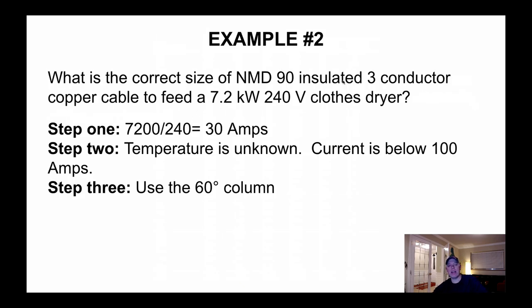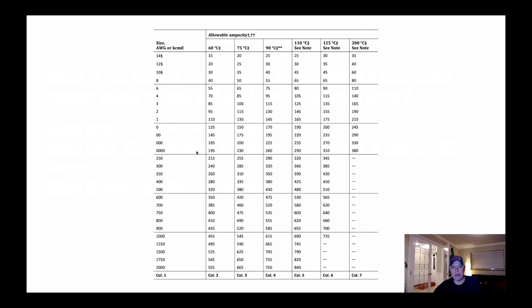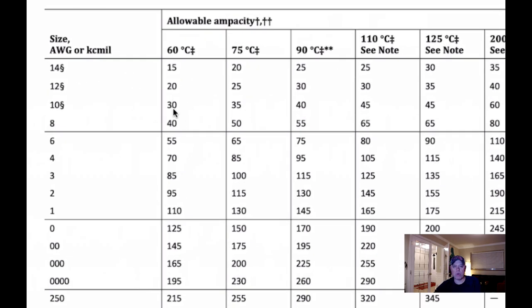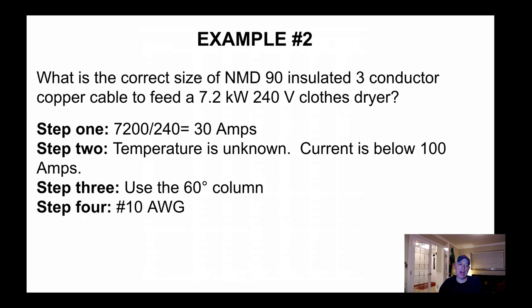Example 2: what's the correct size of NMD, insulated three-conductor copper cable to feed a 7.2 kW, 240-volt dryer? Step 1: take the power divided by the voltage — we get 30 amps. Step 2: temperature is unknown and current is below 100 amps. Step 3: use the 60-degree column for 30 amps — that gives us No. 10 wire. Step 4: the answer is No. 10. There's not a lot to it; it builds on what we covered in the last video on wire ampacity.